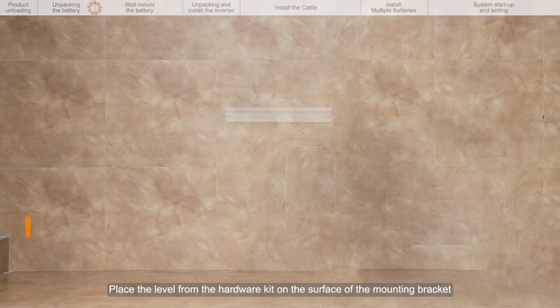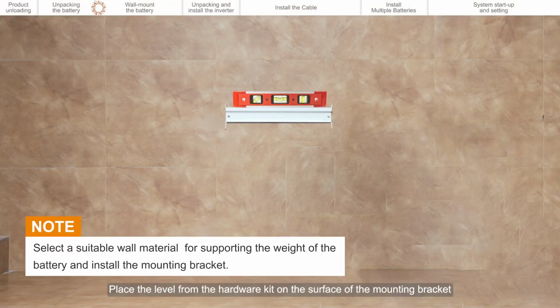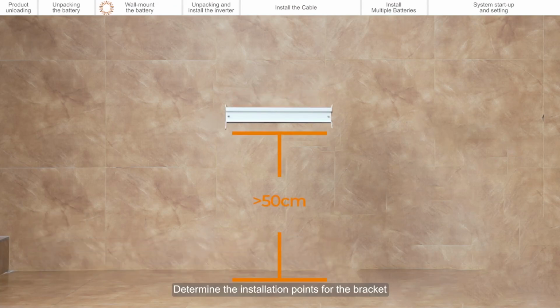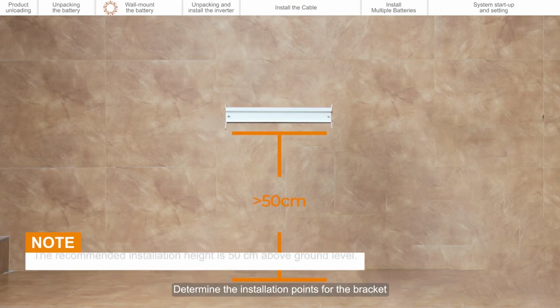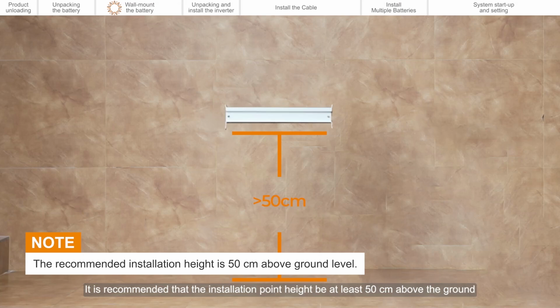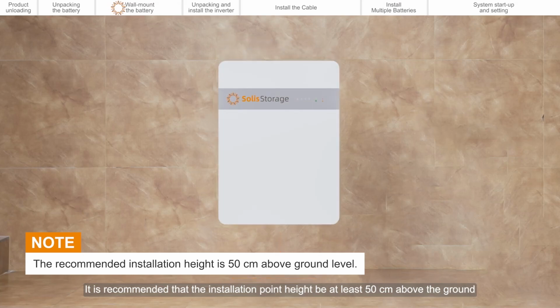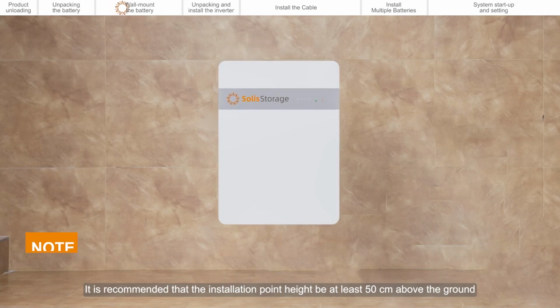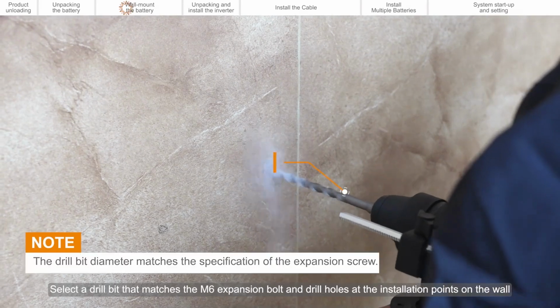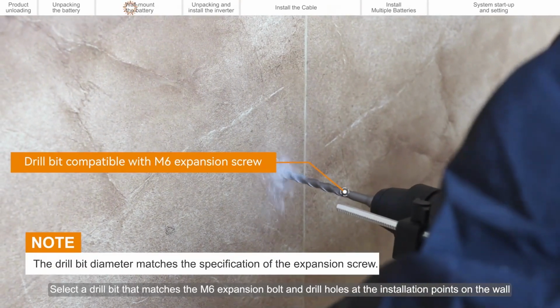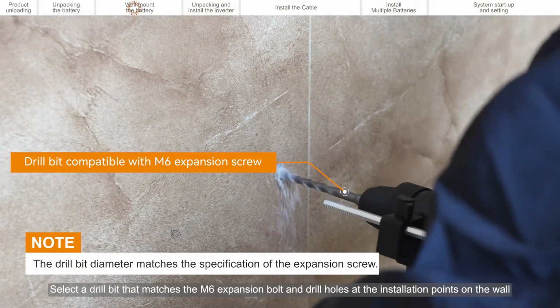Wall mount the battery. Place the level from the hardware kit on the surface of the mounting bracket to ensure the bracket is horizontal. Determine the installation points for the bracket. It is recommended that the installation point height be at least 50 centimeters above the ground. Select a drill bit that matches the M6 expansion bolt and drill holes at the installation points on the wall.